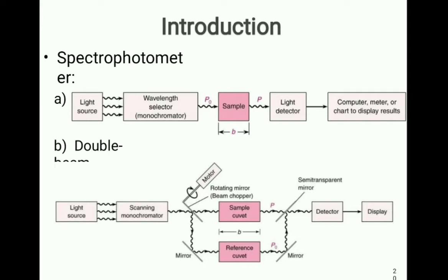Firstly, we have a light source that will produce a polychromatic light. After that, we have a wavelength selector — that is our monochromator — that allows only the passage of a single wavelength. Then we have a sample holder connected to the light detector. This detector will measure the amount of light transmitted and convert it into an electrical signal, which can be seen on a computer or a chart to display results.